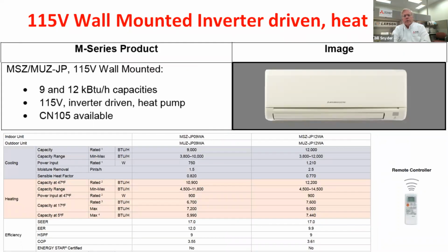Now, last year, Mitsubishi introduced a 115 volt inverter driven heat pump. They used to have a non-inverter heat pump years ago. It was just like a typical unit. The contactor pulled in, the compressor went to 100% and shut off. They stopped production on that, and that was a cooling only unit. This unit is a 115, 120 volt inverter driven heat pump. So it's a one-to-one heat pump.